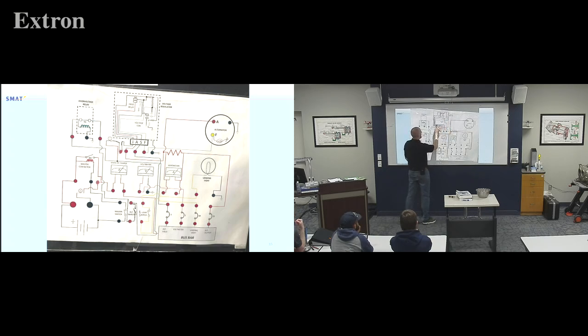So if I trace F backwards, our ultimate goal is to go through those contacts right there to get it to F. That is the ultimate goal of this device: we take power from A, once S says yes, start making power, that closes, it goes through these contacts, out to F, to our field, to give the field a positive voltage and say, hey, give me the maximum voltage.